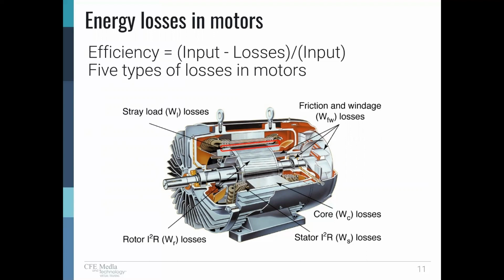We've got stator I squared R losses, and I'm going to try and turn on my little laser pointer here. We've got the stator I squared R in the windings of the motor, and that's embedded in a magnetic steel core. So that's core, where we can have core losses. There's a core in the rotor with some losses there. The rotor also, again, rotating transformer, secondary. We've got an aluminum die-cast rotor, as it's called, so we have aluminum end rings with bars in the magnetic material. So we've got rotor losses there. We have friction and windage. We see the external cooling fan, the bearings, and we also have internal cooling fans. And then we have this stray load loss that, as I mentioned, occurs in the space between the stator and the rotor. There's a slight clearance between the two.